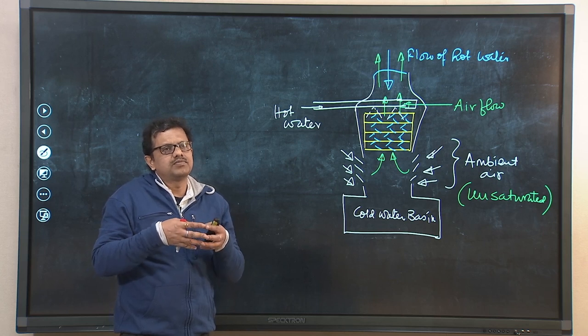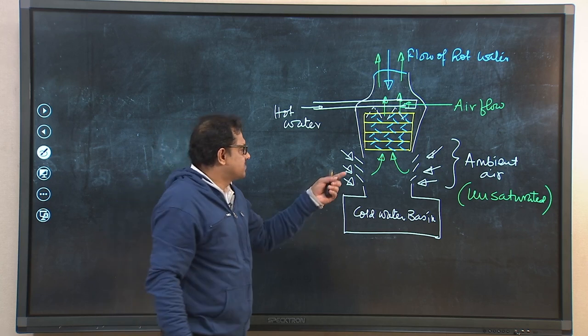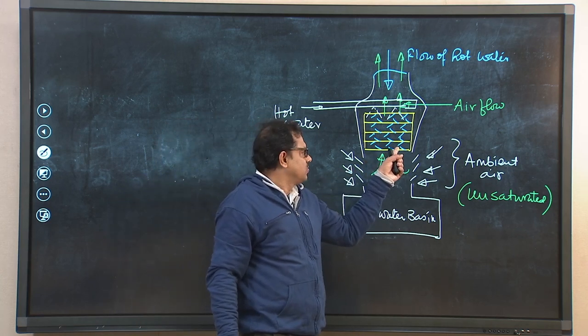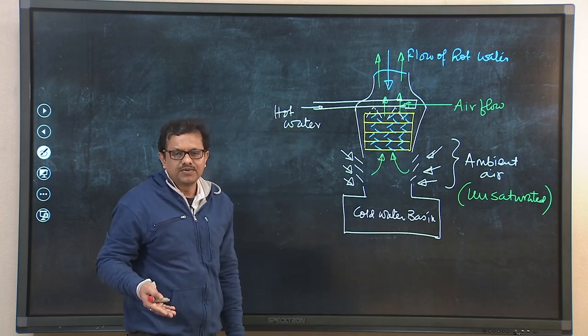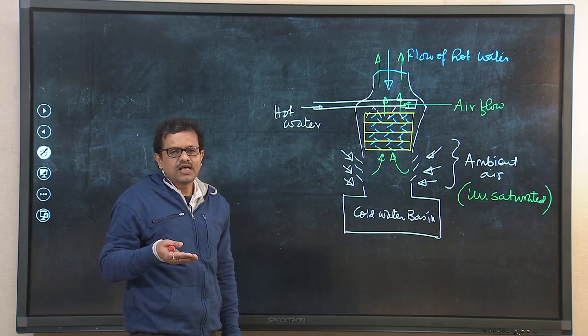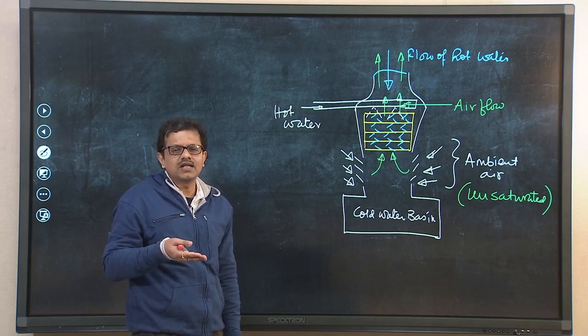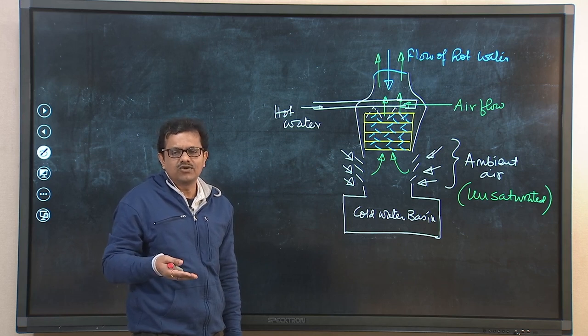These two streams — water and air — mix intimately, and that mixing promotes both heat and mass transfer. Because of this mass transfer, water will be cooled down further through evaporative cooling. As water evaporates, latent heat is taken from the water, its temperature reduces further, and we get more cooling.